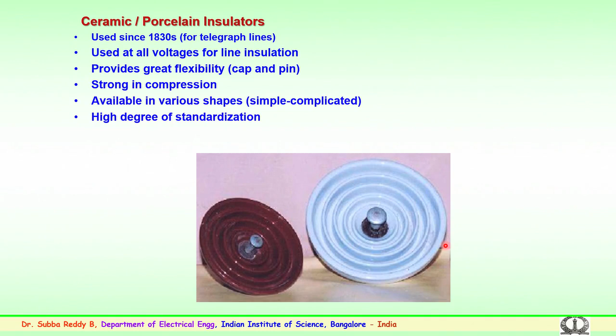You can see the metal pin and the cap surrounded by the porcelain or glass shell. These have a high degree of standardization, with various types and sizes used for various locations. It could be for normal conditions, desert conditions where an aerofoil type of insulator is used, or in conditions of contamination where anti-fog insulators are being used, for HVAC and also for DC systems. Some experience with ceramic insulators was also discussed.